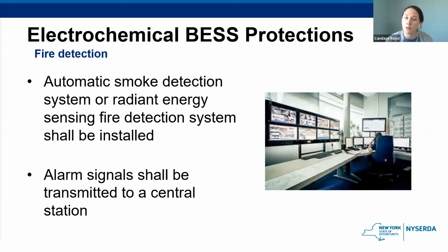So moving along, we have the fire detection requirement. When systems are inside a controlled room or enclosure, the smoke alarm is generally the easiest way to sense a fire. You're going to need some sort of automatic smoke detection system, or it might be a radiant energy sensing fire detection, to be installed. And all of these alarm signals shall be transmitted to a central station.